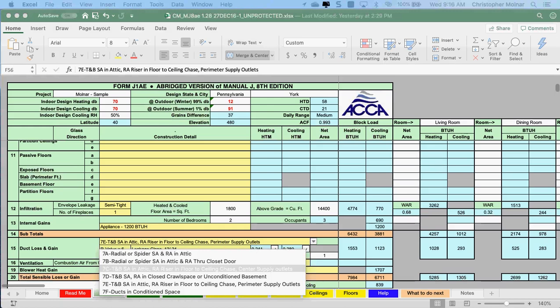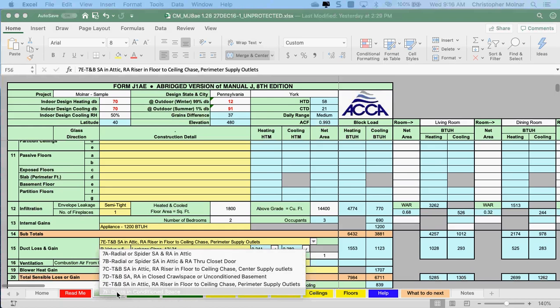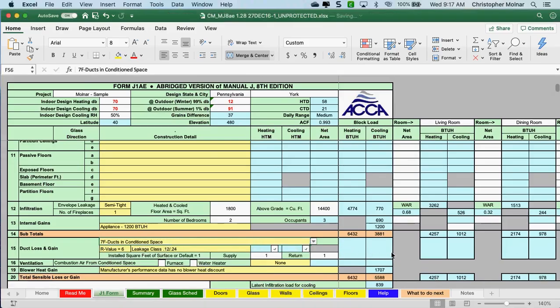Do this as if putting everything up into the attic. You can do the exercise twice — once for the basement and once for the attic — or you can just accept the fact that if we look at the numbers: ducts in a conditioned space gives no heat loss, and going into the attic is only 744 BTUs of heat and 576 of cooling — not even half a ton of difference. Remember, 12,000 BTUs is a ton. You could probably just get away with selecting unconditioned and be fine.